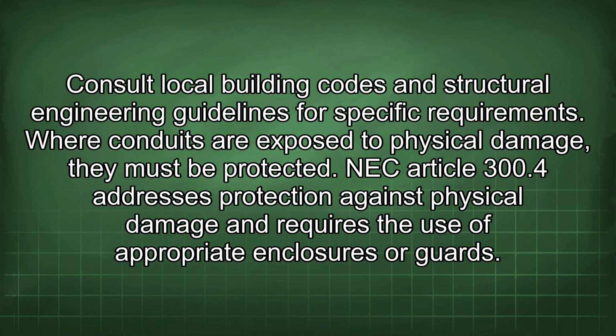Where conduits are exposed to physical damage, they must be protected. NEC Article 300.4 addresses protection against physical damage and requires the use of appropriate enclosures or guards.